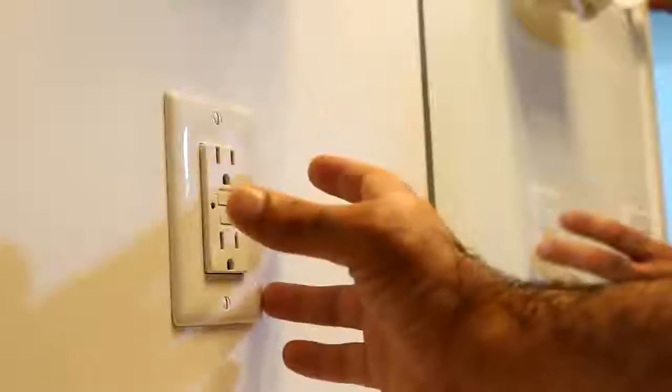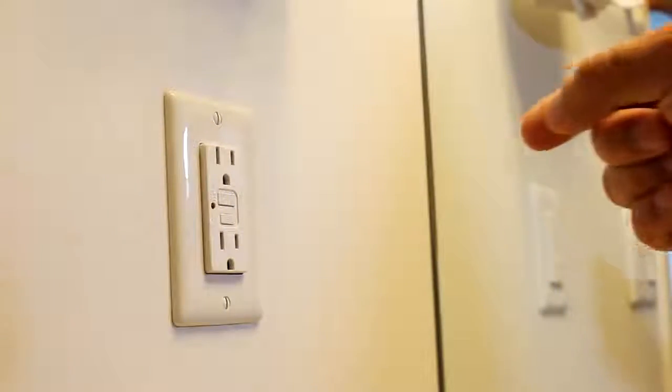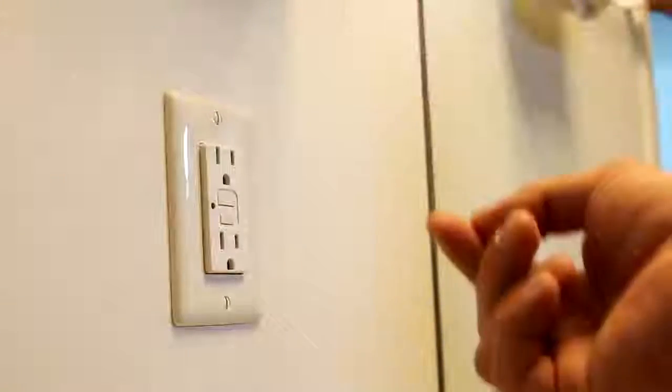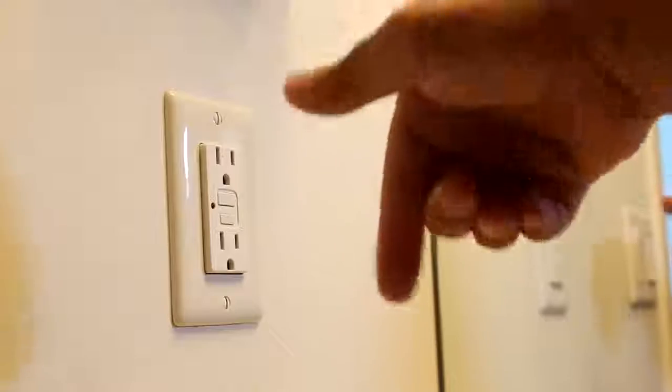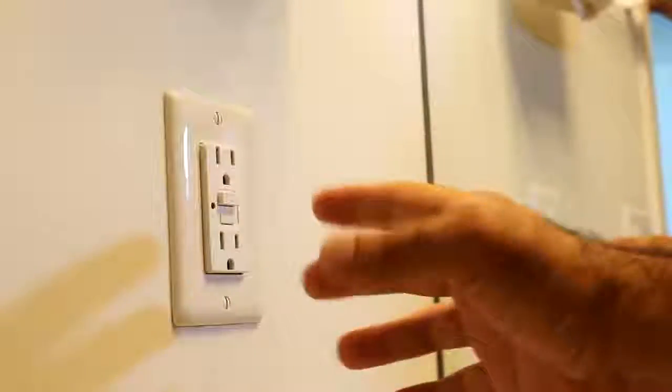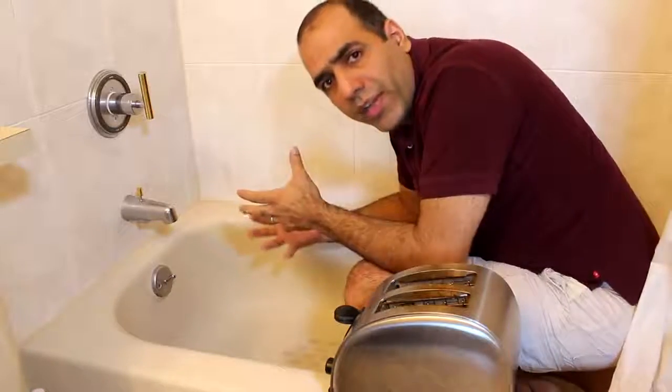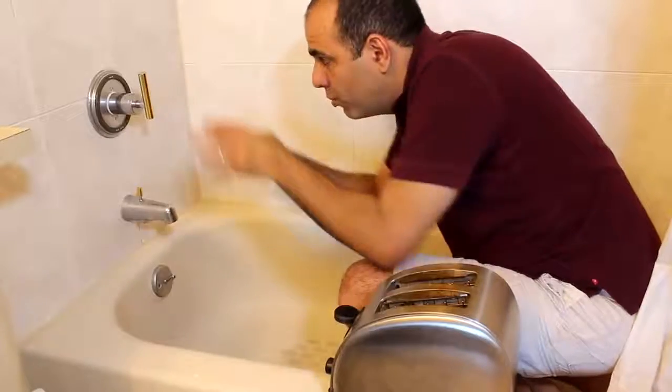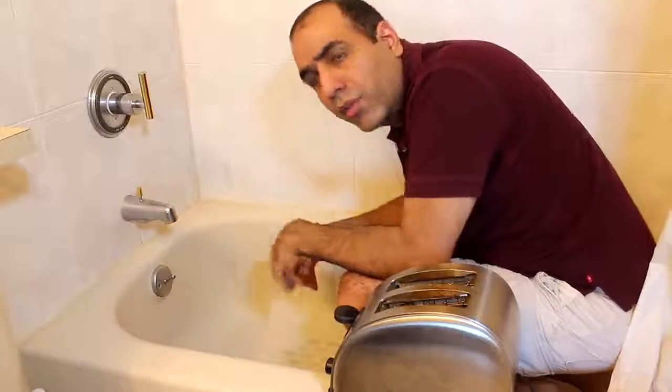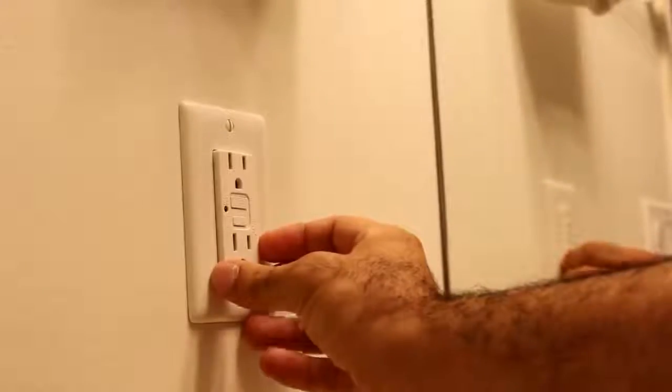What the GFCI outlet does is that it senses the current. Any current that comes out of the live wire must return to neutral to close the circuit. If it comes out of the live wire but doesn't return to neutral, it means that it's going to earth through an unwanted path. The outlet would open its breaker right away to avoid the unwanted current flow. Let's test it out.